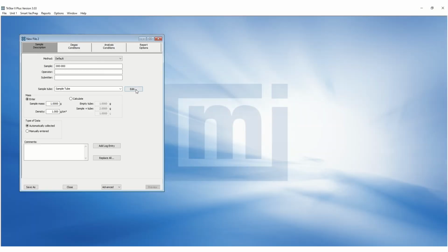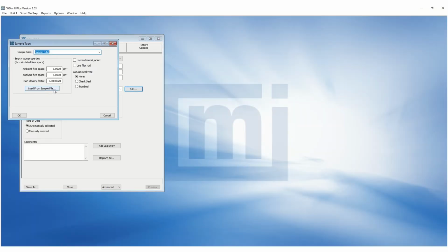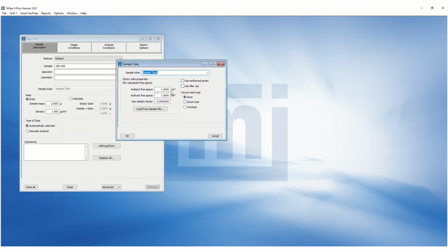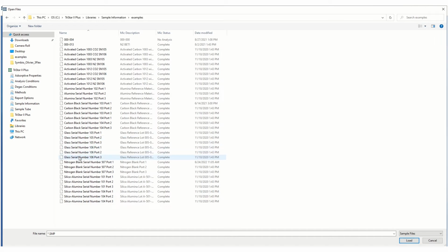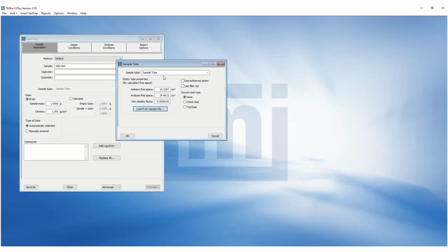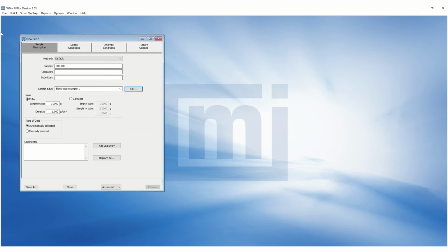Open a new sample file and click on the Edit button for the sample tube, and click Load from Sample File. Browse to load the blank analysis of the sample tube. Once loaded, rename the sample tube appropriately for future reference.